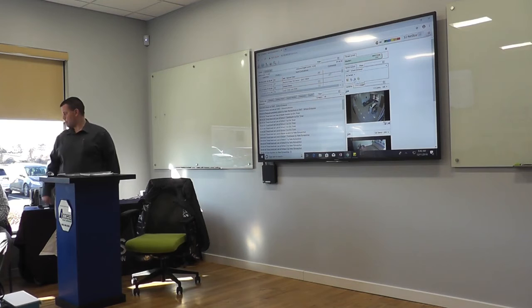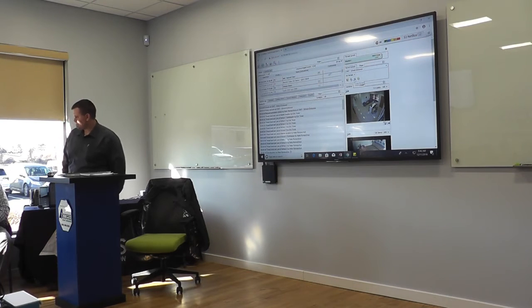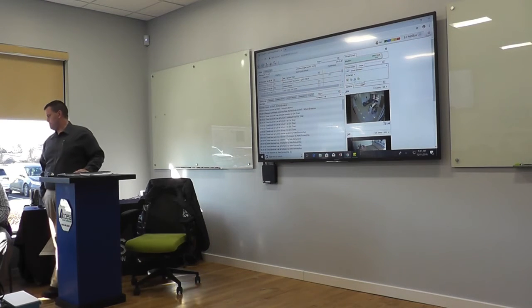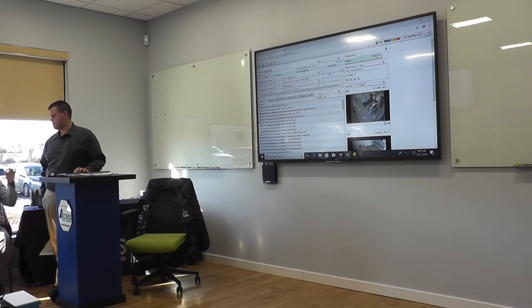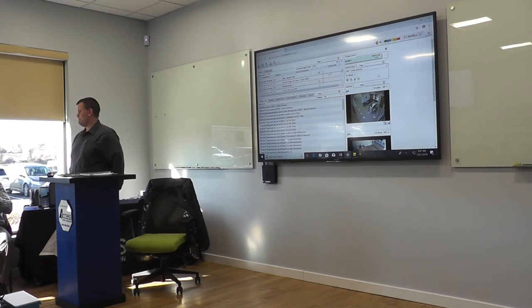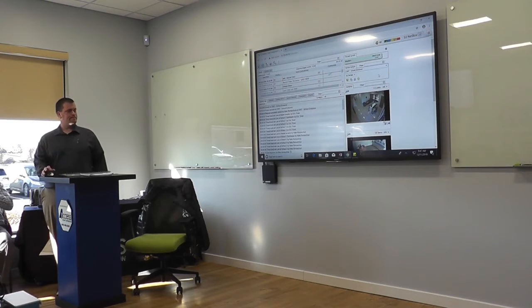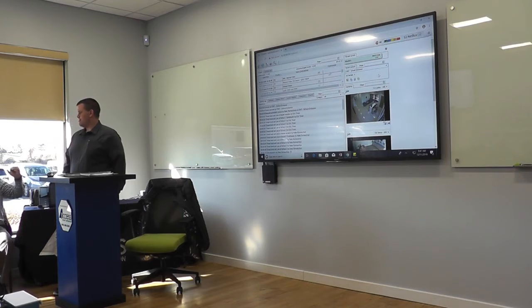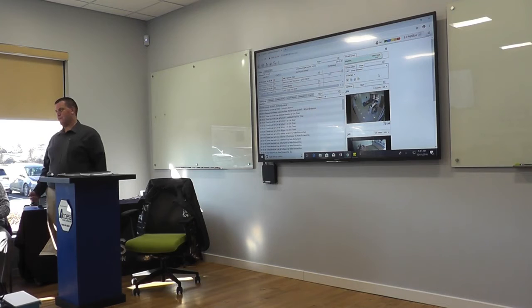I'm really jumping way ahead, and he's going to get to this, but in user roles, you can take that icon away. So I've had customers that kept hitting that by accident, because it looks like an unlock, and they just think they're doing a momentary unlock, and they're doing the extended unlock. And they couldn't get back in. So you can go into the user roles and you can remove that ability for that person when they log in to have that icon appear. He'll take you there, I'm just touching on that since you brought it up. That's a common issue. Yeah, it's a good point.